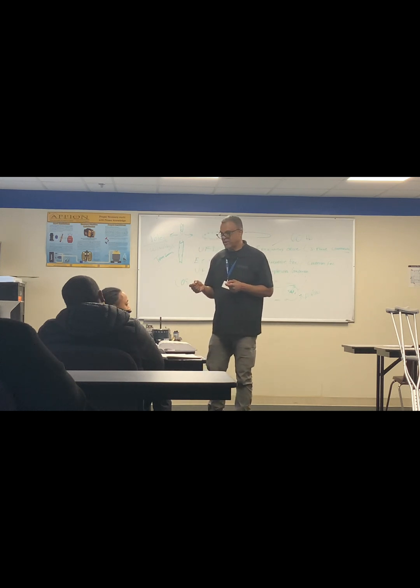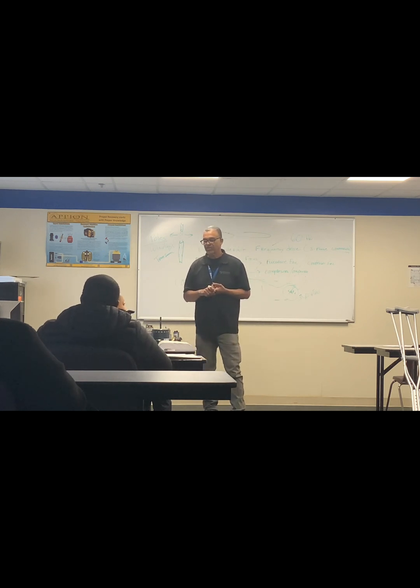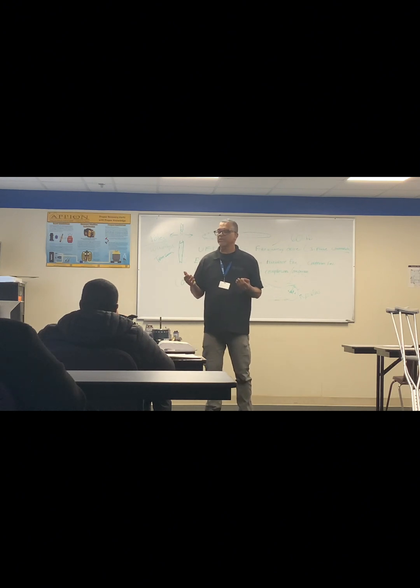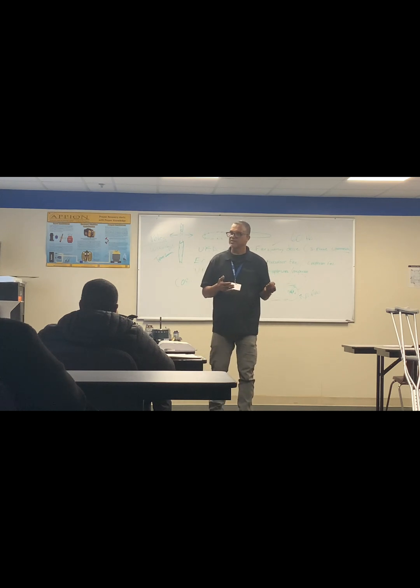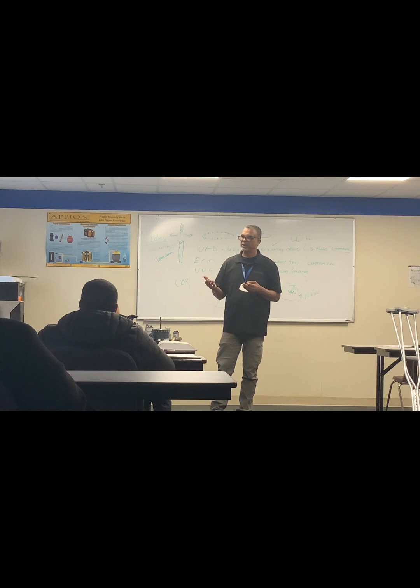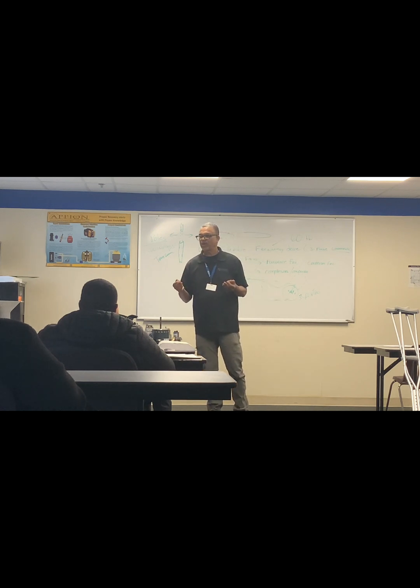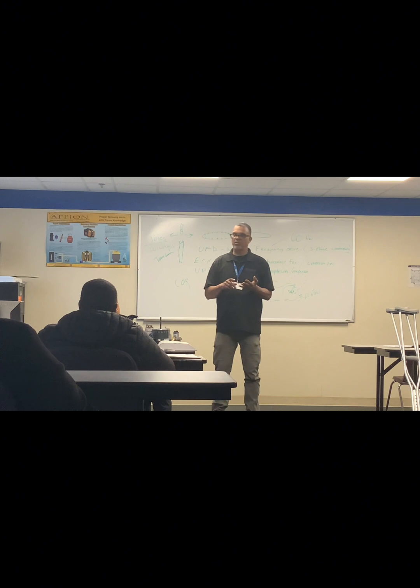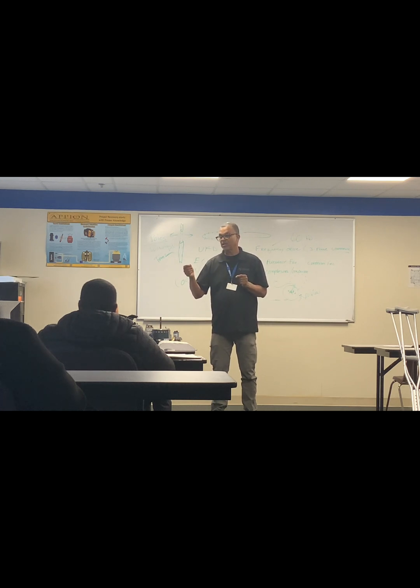And then the other, we always have a set of contacts that's normally open and normally closed. If we want it to close when the coil is energized, then we want a load to operate. So relays are pretty simple in that way: we have a coil, 24 volts, normally open, normally closed. Some of them are just straightforward 4-pin relays, and power goes in and power goes out to the load. So when the relay closes, the fan motor runs.